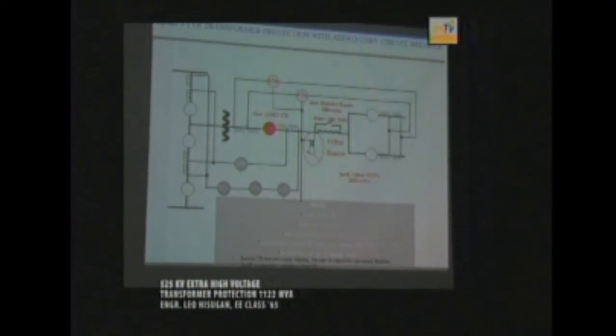So chances are in the next 1, 2, or 3 years, the 63,000 amps will go up to like 70,000. You know? So we need to provide a series reactor on this line from the 525 kV to the breaker in order to limit the short circuit current below 60,000 amps, maybe like 55 or 50,000 amps. So the series reactor there will help mitigate the high short circuit current rating on this 230 kV bus here. On 525 kV, we don't have any problem with the short circuit current capacity, but on the 230 kV we have.